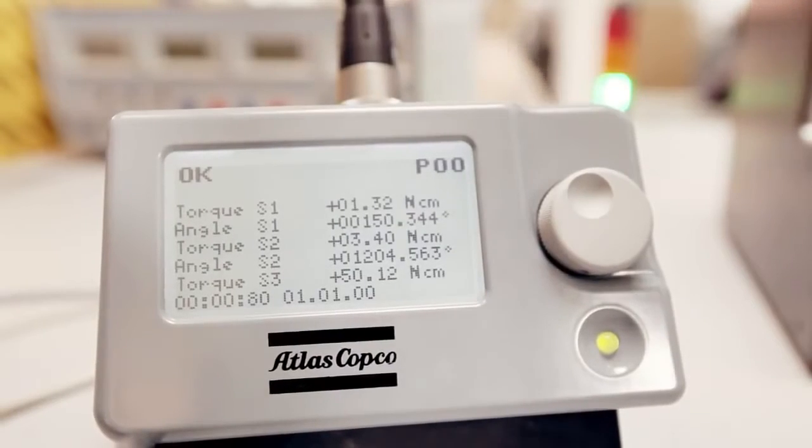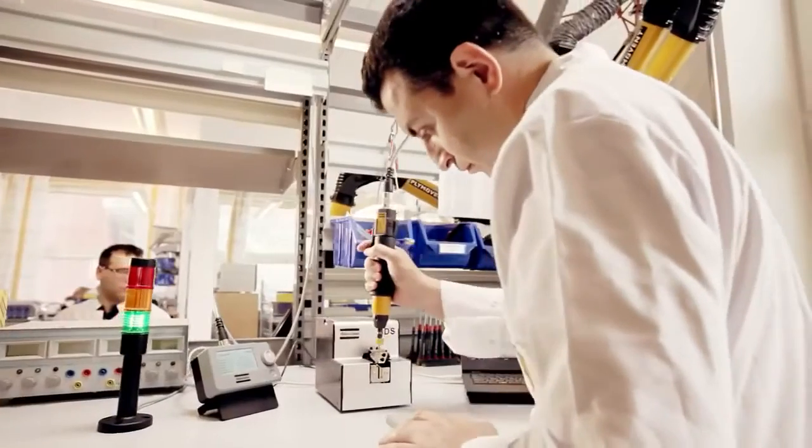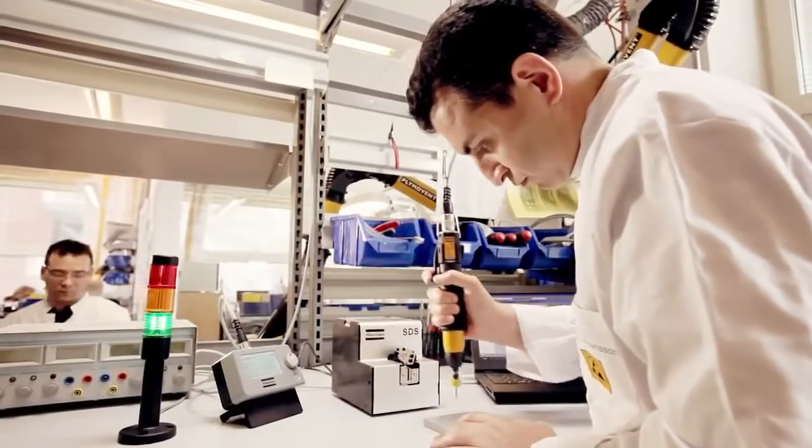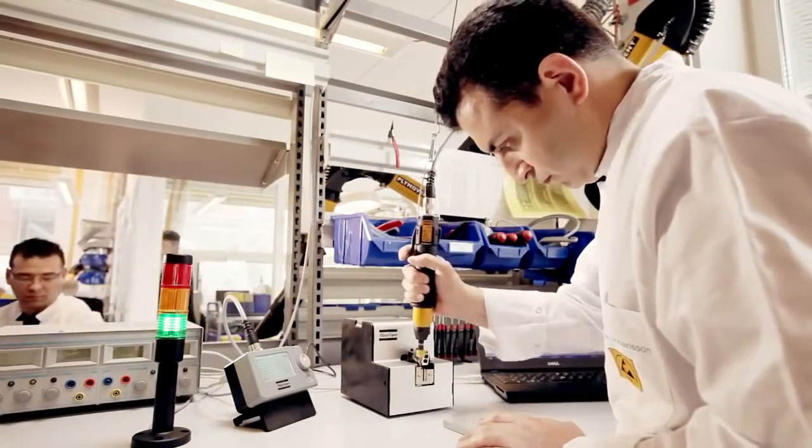Torque and angle monitoring make it possible to detect common assembly problems. The system provides clear operator feedback with light and buzzer signals for OK and not OK tightenings.